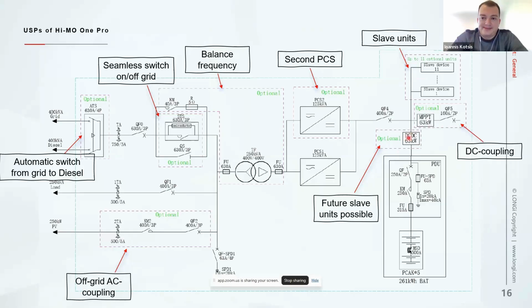Here is the DC-DC converter. This is obligatory if we want to have a slave. So if we want the slave unit, we also have the DC-DC converter. It's inside the cabinet. I want to comment here that if the customer wants, he can add more capacity later. Let's say he can start his installation with maybe 1 master unit and 1 slave. So he will have, let's say, half megawatt hours. Yeah, 500 kilowatt hours capacity. Then he can extend in the future by adding more slave units. And also the integration of the slave units is very easy.